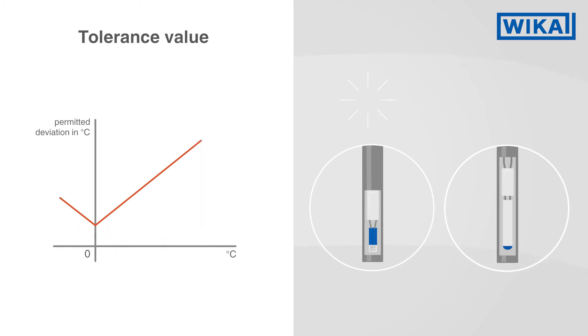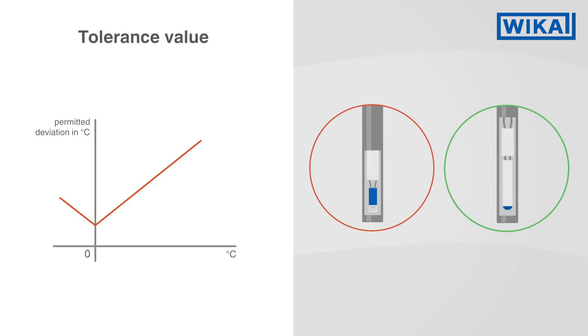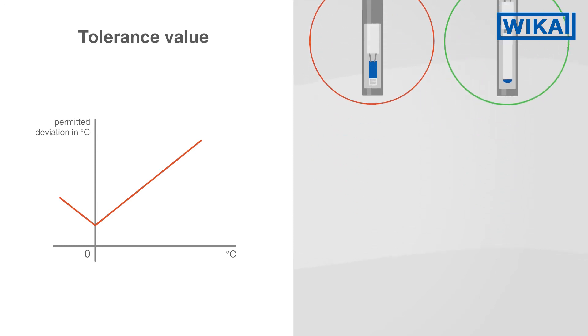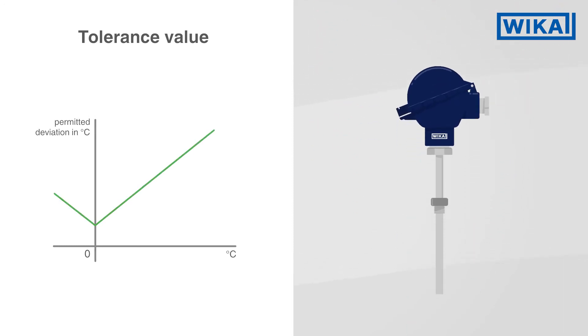The choice between a thin film or wire wound measuring resistor has an effect on the temperature measuring range. Standard resistance thermometers with wire wound measuring resistors in class B are defined from minus 196 degrees Celsius to a maximum of 600 degrees Celsius in accordance with the IEC standard.